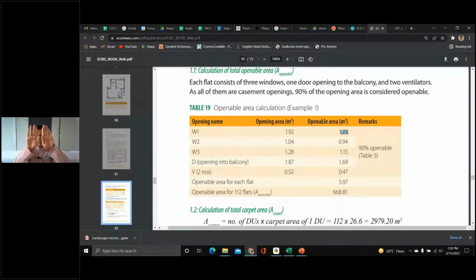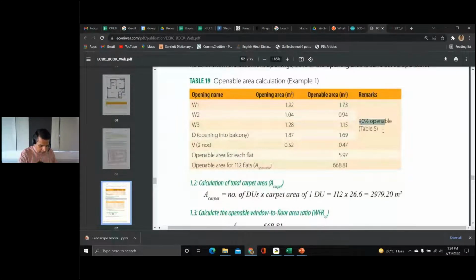is inside the frame and it opens fully and it closes fully. This is not a top hung window, it's not a sliding window, it's none of that. All right, simple window. You can assume 90% of the opening is considered openable. Rest of it will be frame, will be mullion members, so on and so forth. Okay. So here, what have they done? They've taken 90% openable, and for 112 flats, they've directly multiplied it and they've got 668.81 as the openable window area.